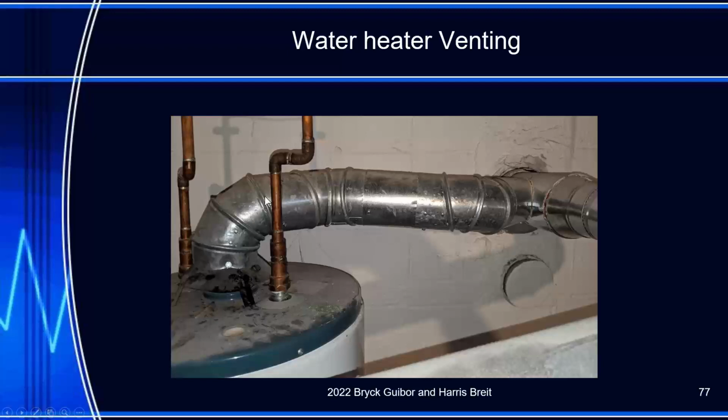Okay, here's my gas flue pipe. Is this lower at this side than this elbow? Yes, it is. Harris, can gas fumes flow downhill? Only uphill. And then if we take a look here, this is single wall pipe. I thought I had to have type B pipe when it's exposed. Only when it goes through an attic or combustible, a thimble, or some place where I can't see it per se.